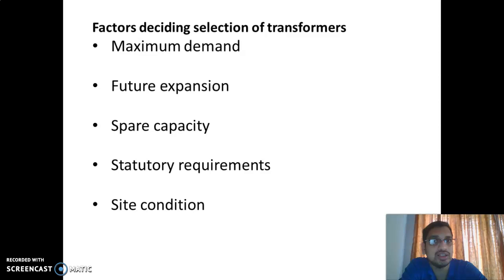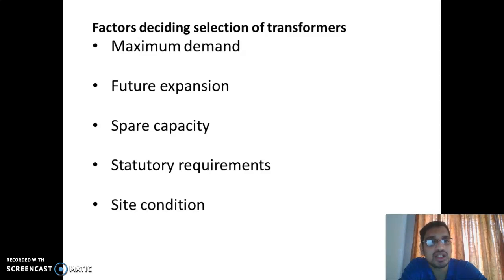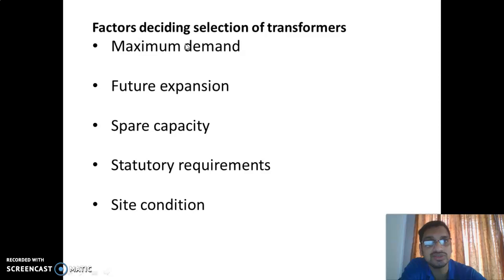The sizing of a transformer can be done by calculating the connected load. First, we calculate the connected load of the industry — we consider all the motor load, all the light load, all types of loads. After calculating the connected load, we then calculate the maximum demand. The size of the transformer is decided by the maximum demand, and an industry installs the transformer based on its maximum demand capacity.